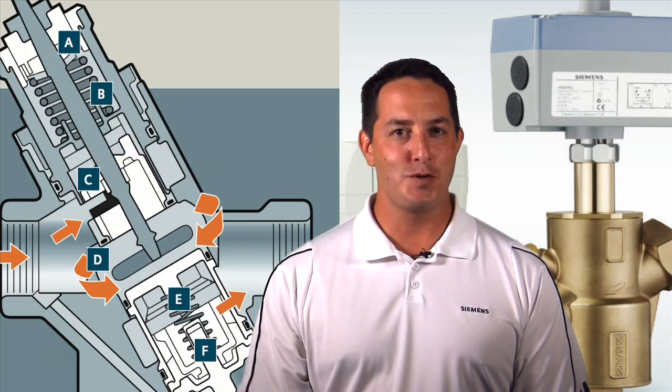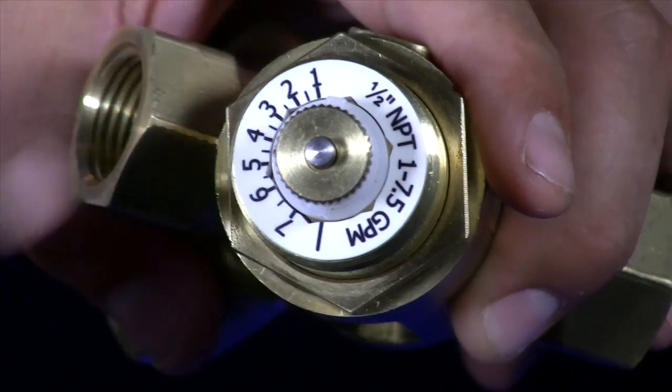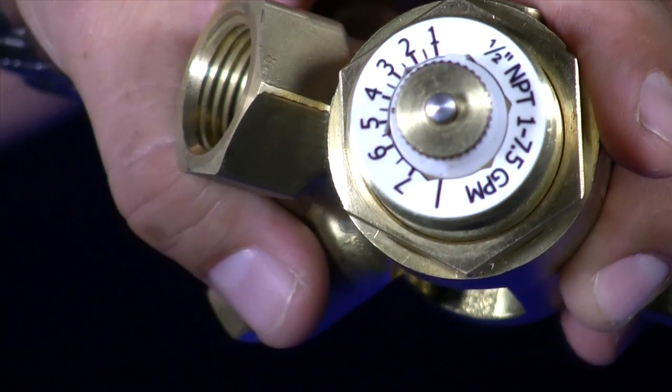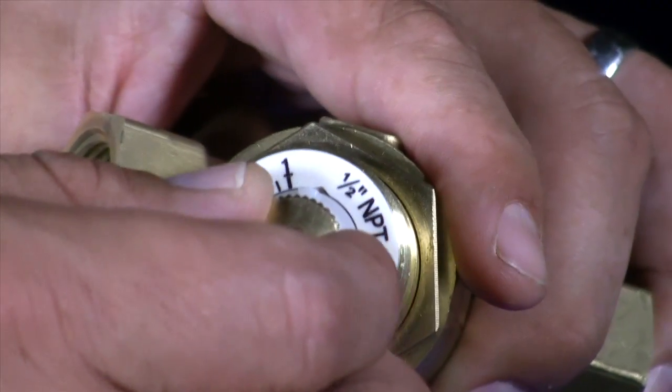So now I would like to show you why the Siemens PIC valve is so special. The first thing you'll notice with the Siemens pressure independent control valve is the flow limiter. It's its own separate component unlike other manufacturers. It's very, very simple to dial in the desired GPM that you need for your system.